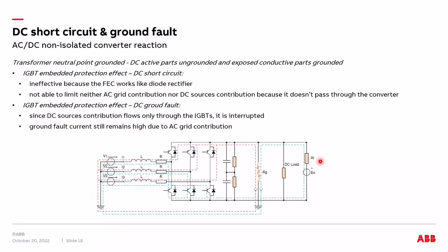Instead, in case of a ground fault, as you can see in this schematic, if we rely on the internal IGBT protection, we can open the IGBTs, which means that we can interrupt the contribution coming from all the other battery systems in parallel, the batteries of electrical vehicles, if the DC-DC chargers are not isolated, and also the contribution coming from the DC capacitor. But we still have the contribution coming from the AC grid passing through the upper freewheeling diode. So we still need suitable protective devices on the DC side.